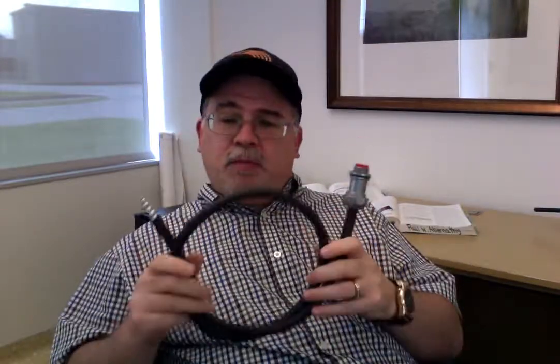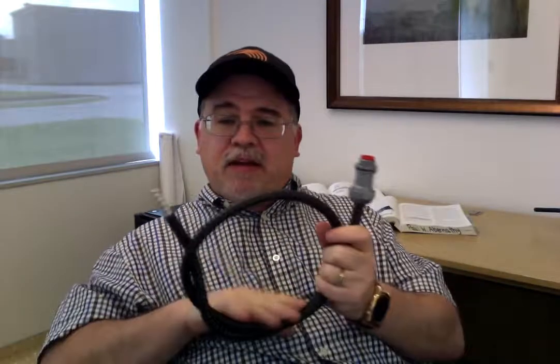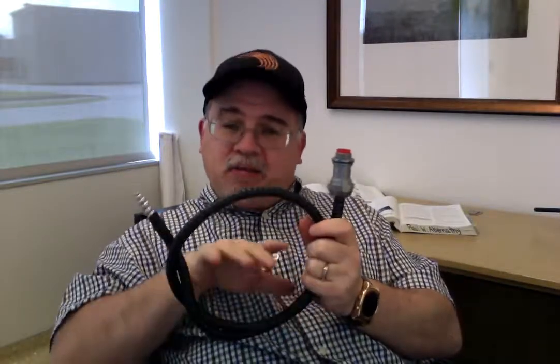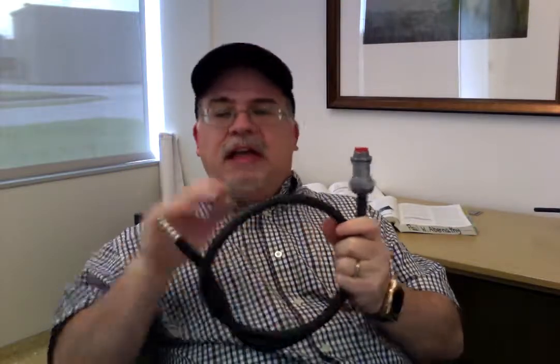Then you'd need this type of fitting. Keeps moisture from getting into the ends and into the equipment. Now, what about if I'm using this product in a wet location, but the resulting terminations end up in a dry location? Then I can use a standard fitting for the termination here because it's in a dry location. This fitting is not being subjected to a wet location. But the cable itself might be running through a wet location. Then that's acceptable because this is impervious to wetness and it is rated and identified for a wet location. If the termination is in a wet location, then I have to have this type fitting. If it's in a dry location, just the termination portion, I can use a standard dry location type fitting.